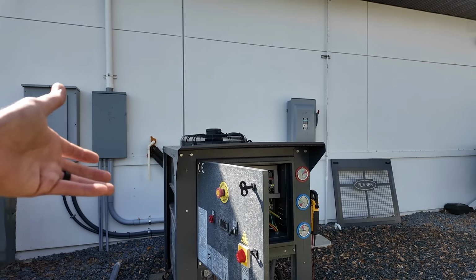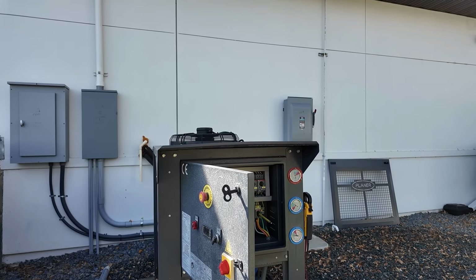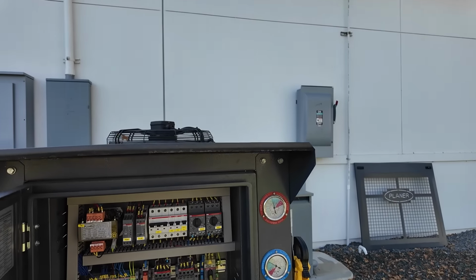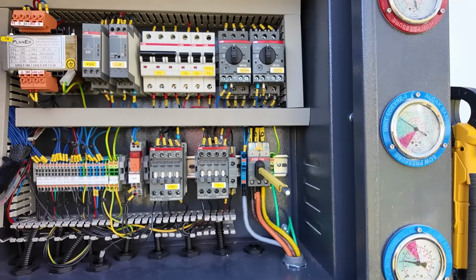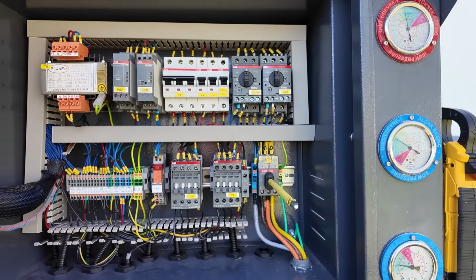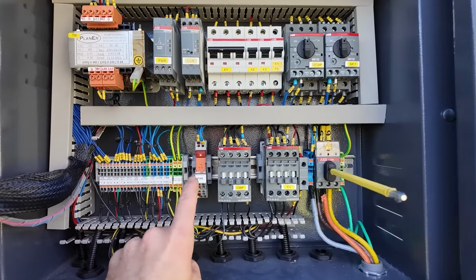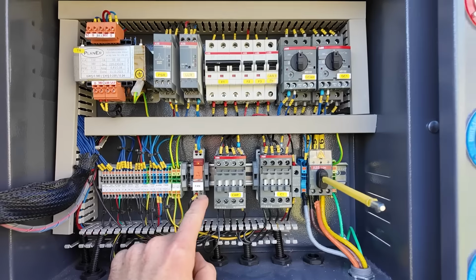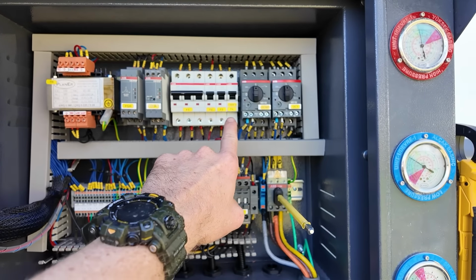In cleaning the outdoor coil, it was filthy, could have been maintained a little bit better. Reset the system and turn it back on again, only to come to find out that the head pressure climbs, but nothing, the fan motor does not come on. You'll see here, I've got a fan relay down here in the bottom left. I've got a fan breaker up here in the top right.